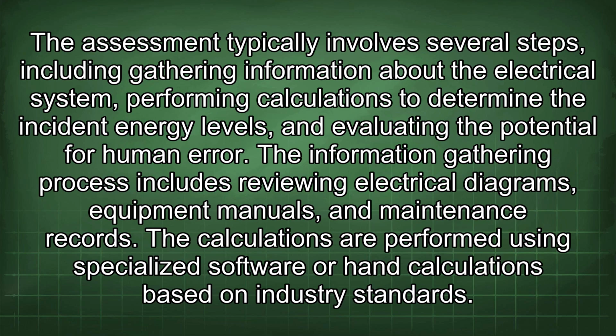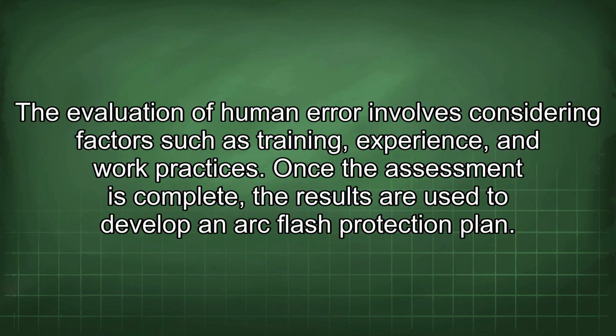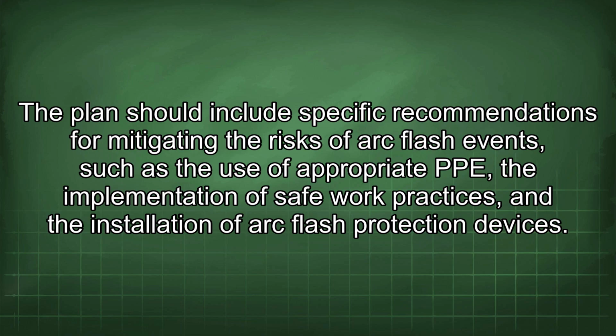The assessment typically involves several steps, including gathering information about the electrical system, performing calculations to determine the incident energy levels, and evaluating the potential for human error. The information gathering process includes reviewing electrical diagrams, equipment manuals, and maintenance records. The calculations are performed using specialized software or hand calculations based on industry standards. The evaluation of human error involves considering factors such as training, experience, and work practices. Once the assessment is complete, the results are used to develop an arc flash protection plan. The plan should include specific recommendations for mitigating the risks of arc flash events, such as the use of appropriate PPE, the implementation of safe work practices, and the installation of arc flash protection devices.